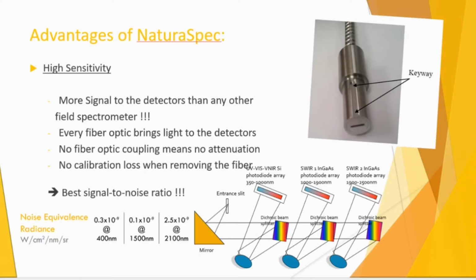The way we do that is that the fiber optic cable of our instrument mates directly with the entrance slit of the spectrometer. So there is no division inside the spectrometer. The complete signal passes through each detector. So our signal is very high going into the detector. Another factor that is important in a fiber optic is whether all the fibers within that cable are contributing to the signal. A typical fiber optic cable has about 60 fibers, so we want to make sure that all 60 of those fibers are bringing the signal to the detectors.